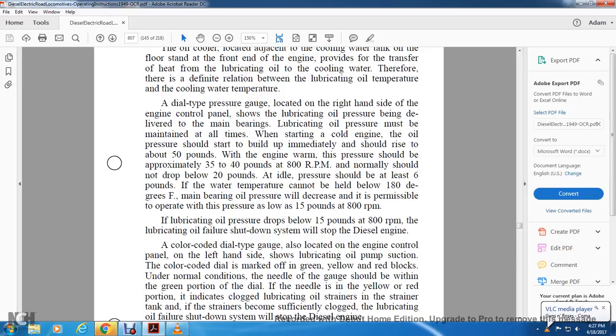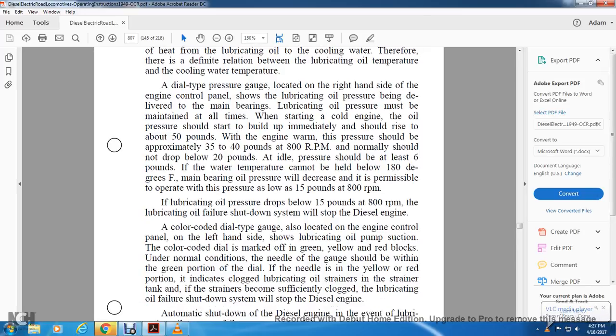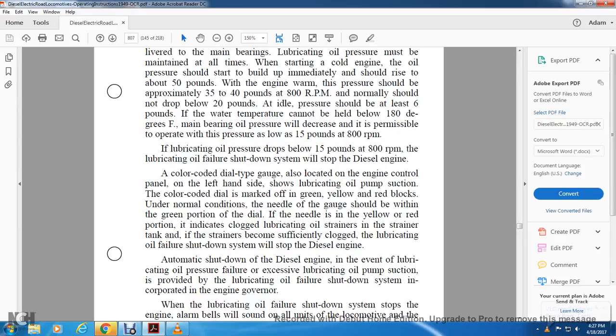If the water temperature cannot be held below 180 degrees, the main bearing oil pressure will decrease. It is permissible to operate at pressure as low as 15 pounds at 800 RPM. If lubricating oil pressure drops below 15 pounds at 800 RPM, the oil pressure failure shutdown system shall stop the diesel engine.